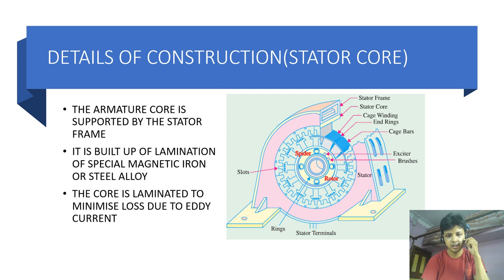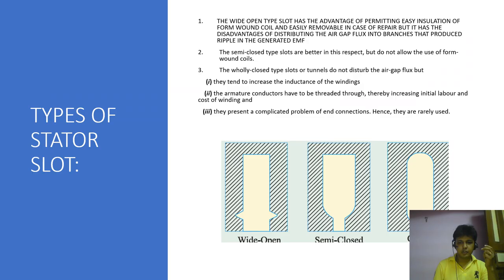The armature core is supported by stator frame and build up of lamination of special magnetic iron or steel alloy. The core is laminated to minimize loss due to eddy current. The lamination are stamped out in complete ring for small machine and in segment for larger machine. The lamination are insulated from each other and have spaces between them for allowing the cooling air pass through it. The slot for housing the armature conductor lie around the inner periphery of the core and are stamped out at the same time when lamination are formed.